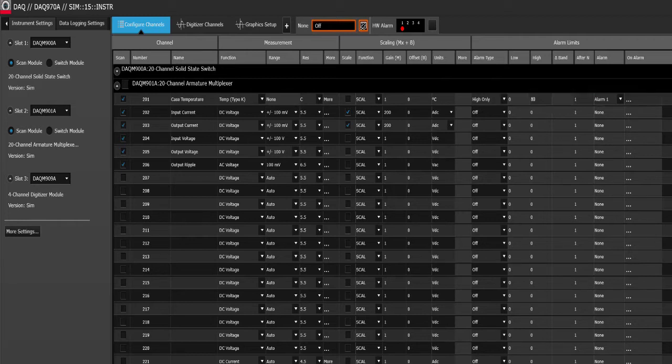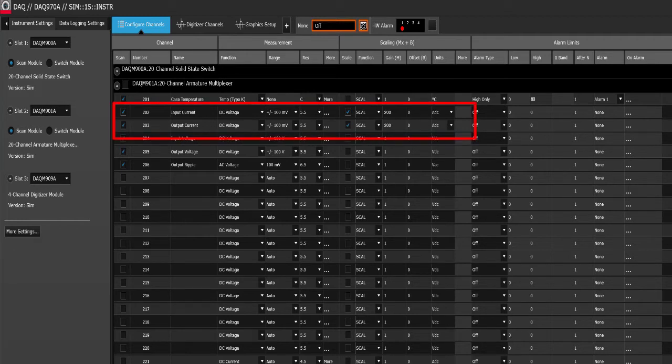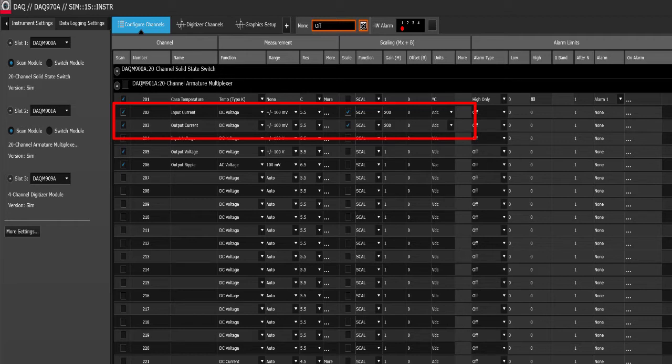Of particular note in the scaling factor, notice that channels 202 and 203 are measuring DC voltage, but we want them to be input current and output current. So using Ohm's law, we will multiply the voltage by 200 which is 1 over 0.005 and convert the output into amps.